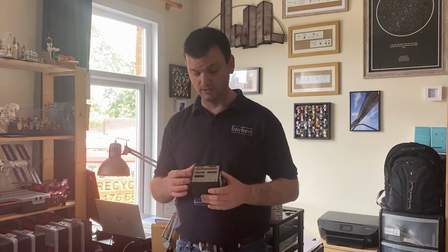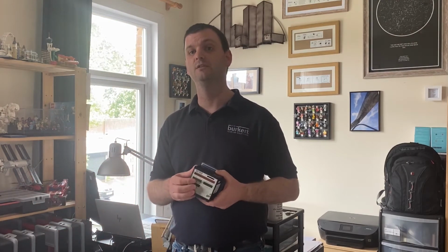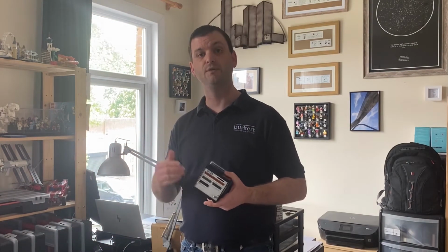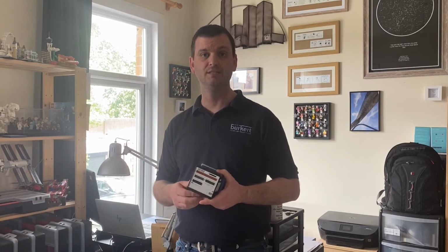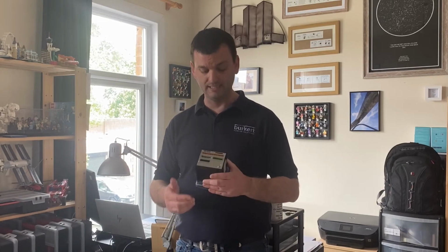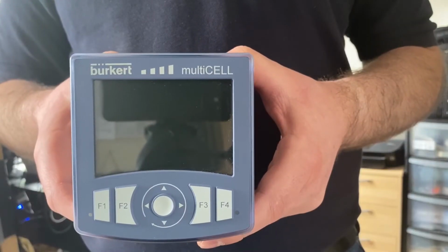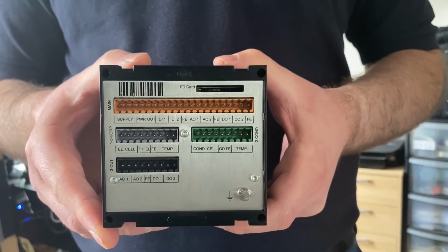So as you can see, Type 8619 is quite a flexible platform, and it's for this reason I'm able to work with a number of different clients with a number of different applications. For example, the latest one I'm working with is a reverse osmosis skid builder, and they want to be able to monitor conductivity at 3 separate points across the skid. For the Multicell, this is no issue because we can simply add in 3 conductivity cards. But the client also wants the option of offering pH balancing before the reverse osmosis system. So we've offered an additional pH card to be fitted in next to it, and then they can take all that information out via analog output or even Ethernet output as well.